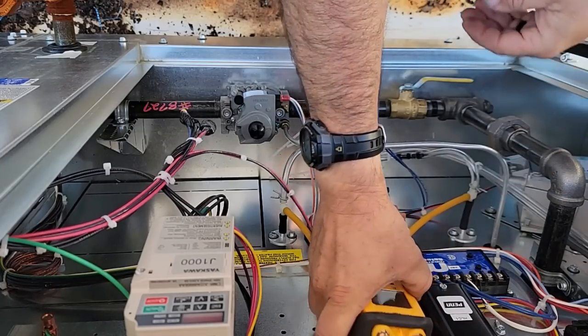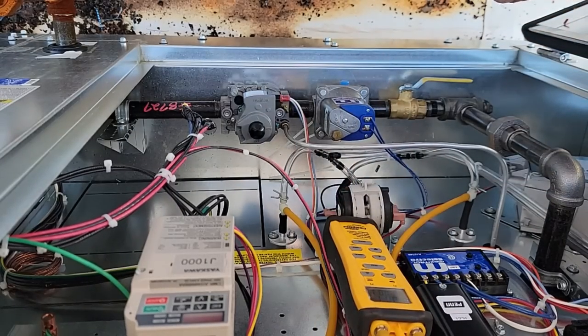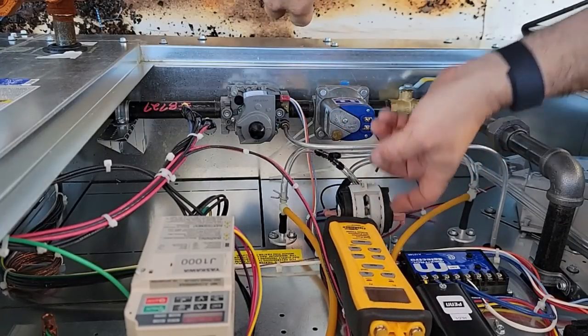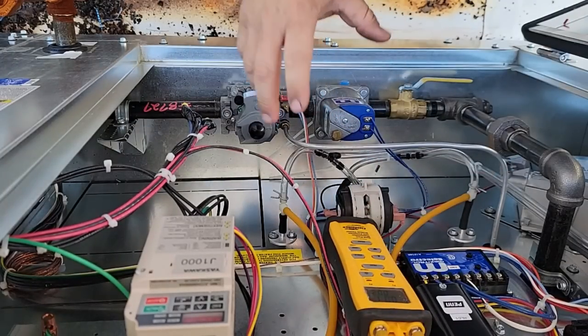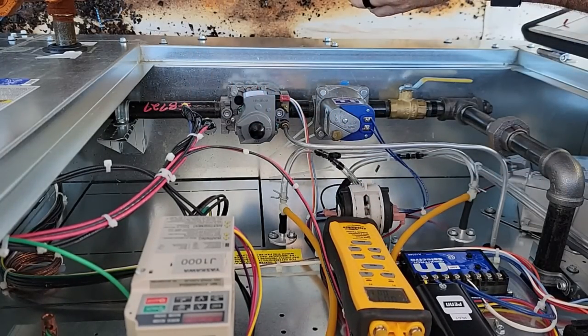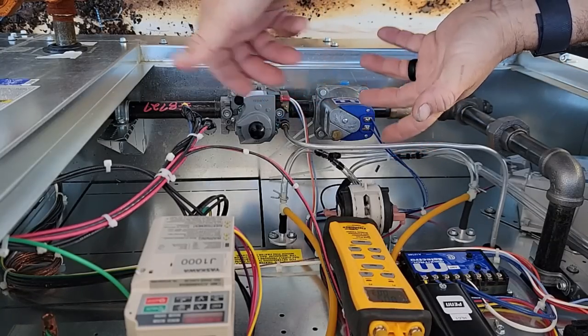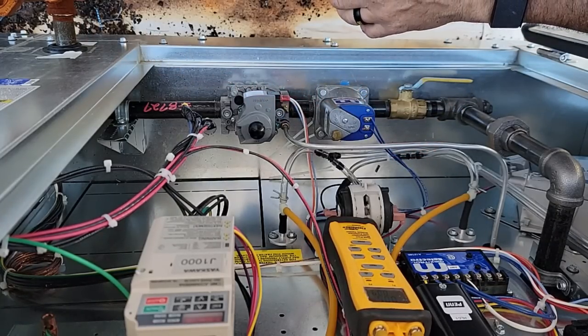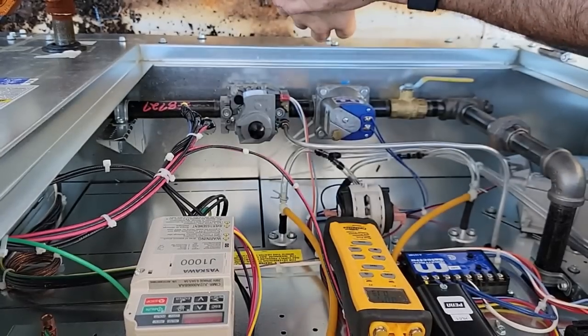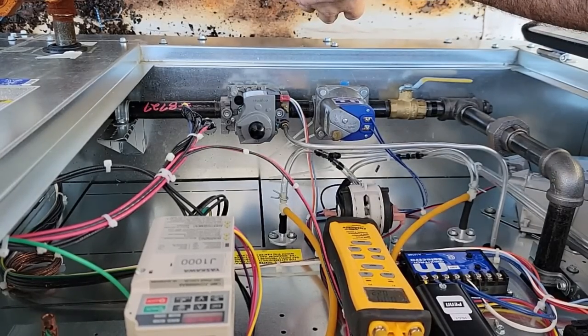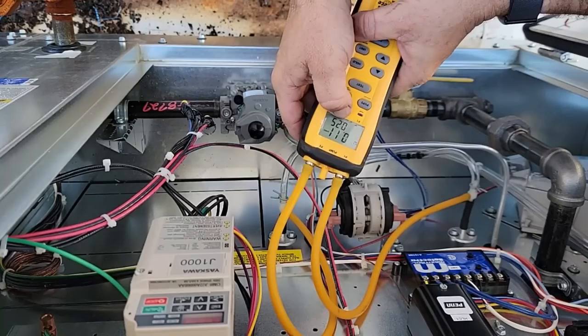Since they're really not wanting it truly set up, we're just gonna get our static pressure set so that at least it'll fire and run. That could have changed since the factory because of the static pressure on the ductwork. I don't know why we're running 80 hertz though, it just seems awfully fast. So we're running right now at a 0.25.